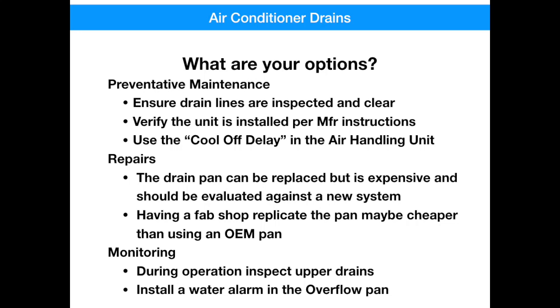Also ask your technician if your air handling unit has what's called a cool-off delay. This is a setting that will let your house fan run for a minute or so after the AC compressor is stopped. This moves the residual cooling left in the evaporator coil into your house and allows for some of the moisture in the evaporator to dry out.